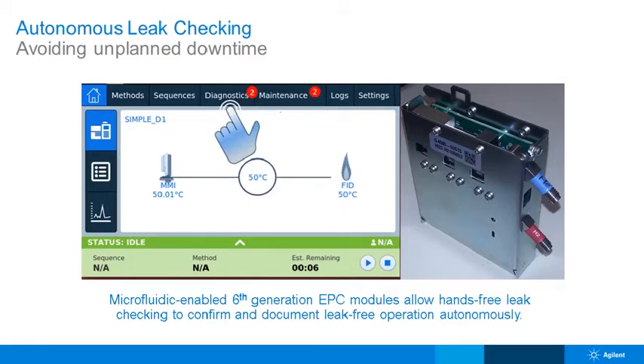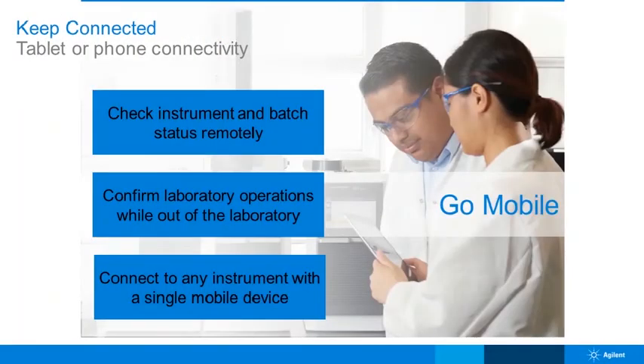So when you're actually changing even something as simple as a liner and you're putting a new liner in, you know it will automatically do that leak check, and you know as an operator that as a result of you doing that maintenance, your analysis will not be impacted. In fact, it's going to work first time, and something silly hasn't stopped you losing an over the weekend run or an overnight run.